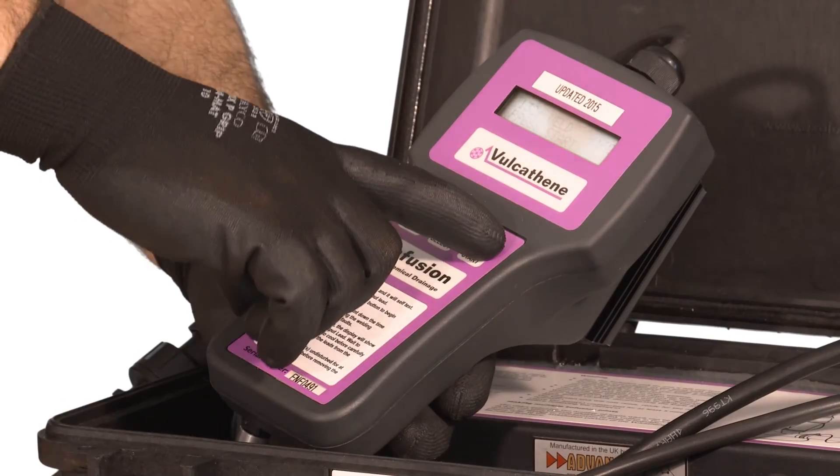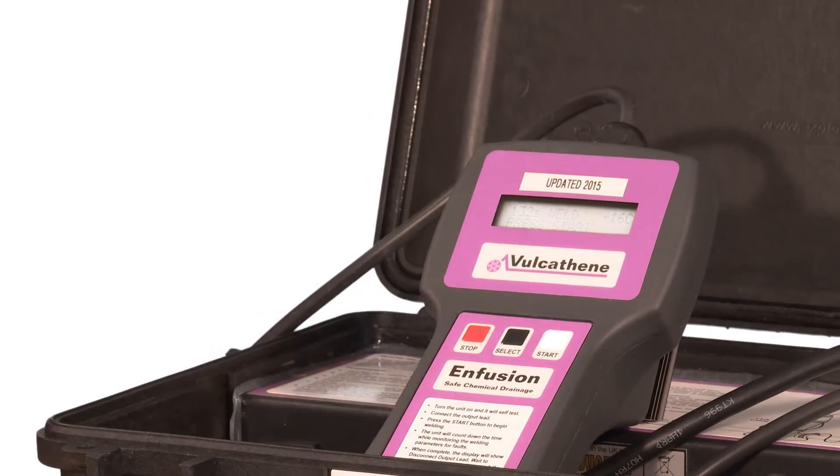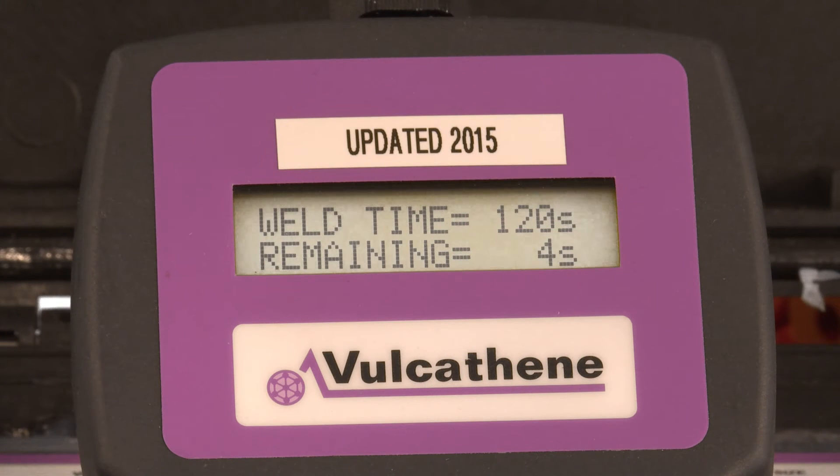The unit will display the temperature and fusion time. The fusion time is dependent on the ambient temperature, which is measured by the unit's temperature sensor. Press the start button and the Enfusion control unit will commence fusion, providing a visual countdown display of the time left to fusion completion.